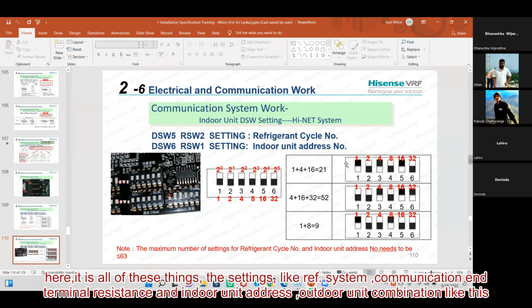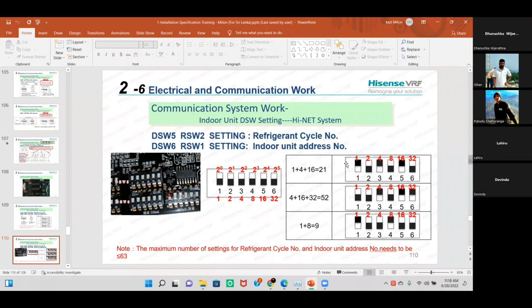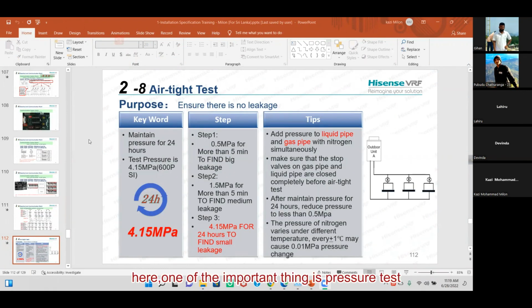Later, here are all of these settings, like refrigerant system, communication and terminal resistance setup, indoor unit address, and outdoor unit combination DIP switches, like this. Here, one important thing is the pressure test.